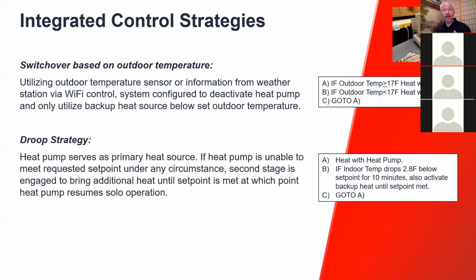Now, that might be fine, but there's a couple of assumptions there. How did you pick that magic temperature? How much time did you, as the installing technician, spend assessing what the appropriate temperature was for that switchover? Could there be circumstances where it's exceptionally windy, and the heating degree is higher because of the wind factor, and so the load on the building is greater?